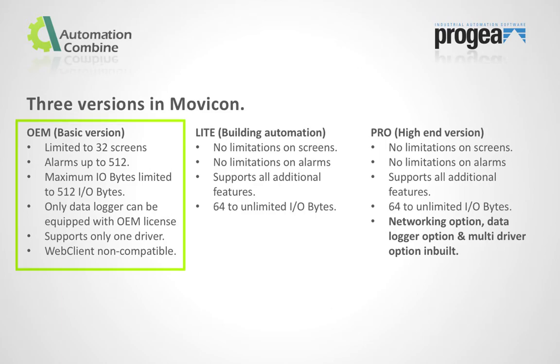The OEM version is the basic version with limited features. In OEM, the number of screens is limited to 32, alarms up to 512, and maximum I/O bytes limited to 512. Since OEM is the basic version, of the additional features only the data logger can be equipped, and it supports only one driver.